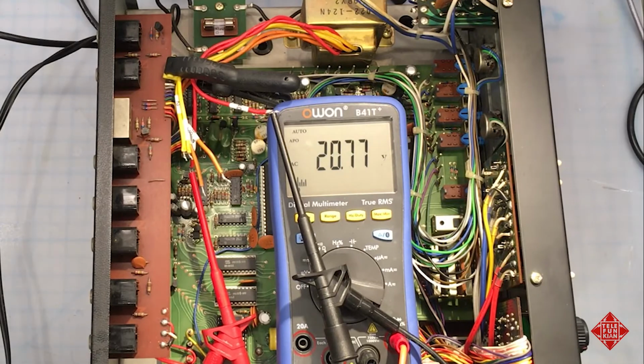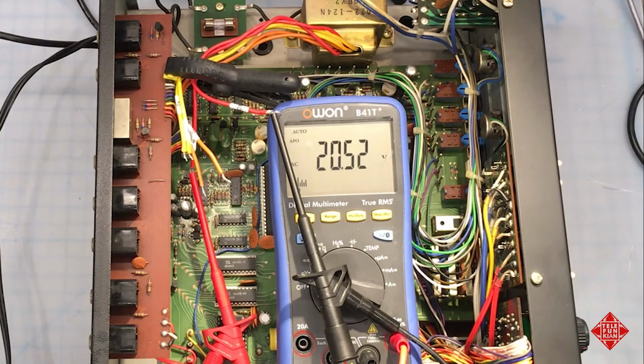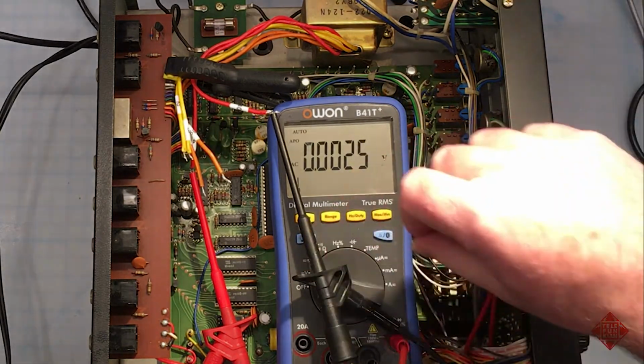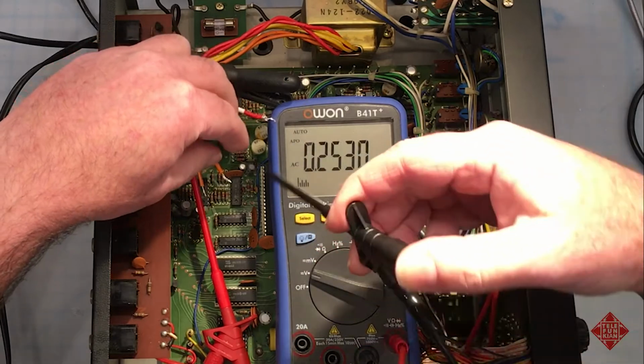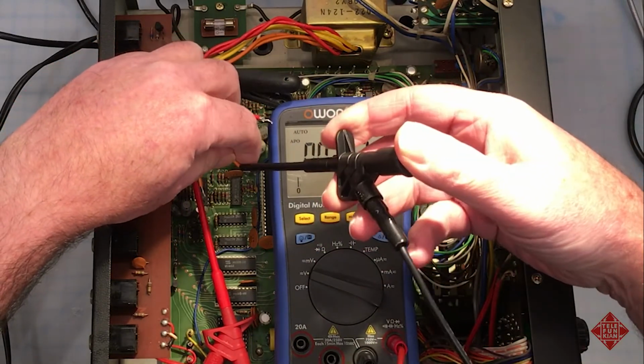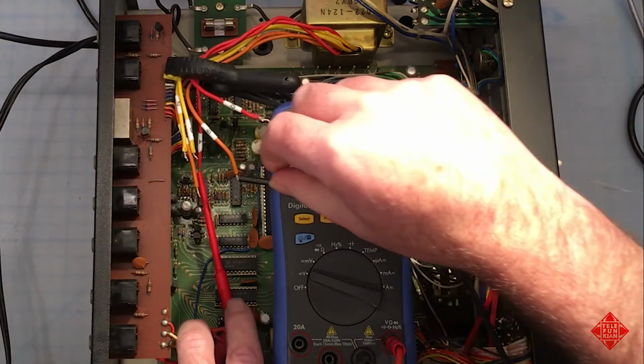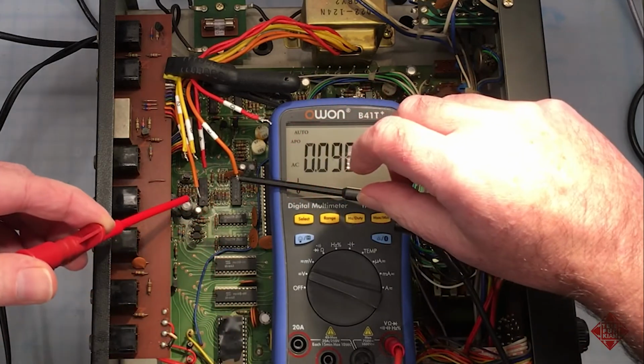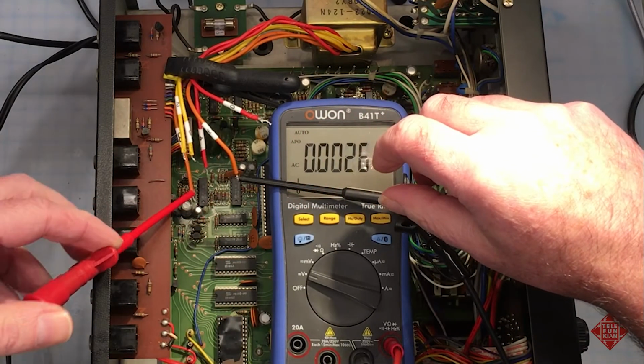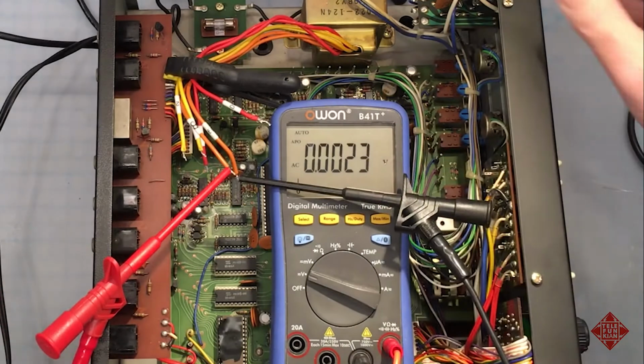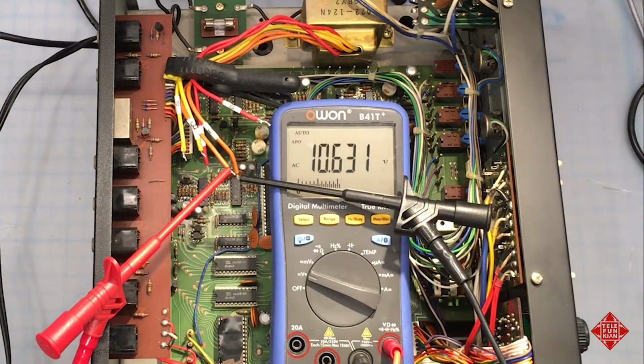I've measured the output voltages of the transformer when it was connected to a variac set to 100 volts and the transformer windings were unloaded. The transformer supplies about 20.6 volts AC across the red windings, 10.6 across the orange, and 10.1 across the yellow when unloaded. We can estimate that the loaded voltages will be about 10% less than the unloaded voltages.